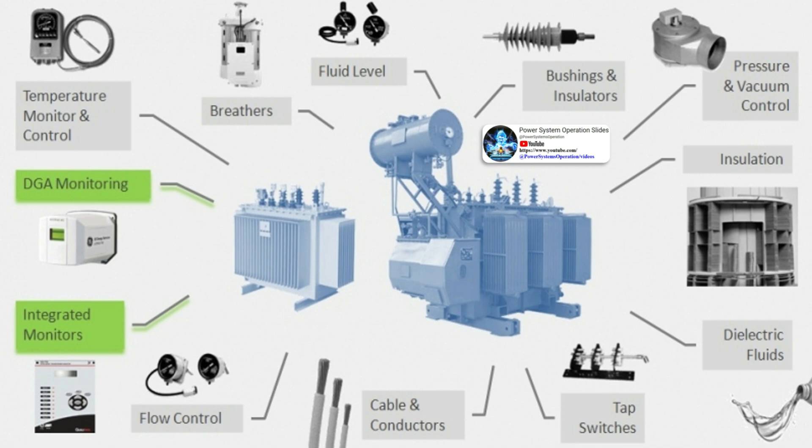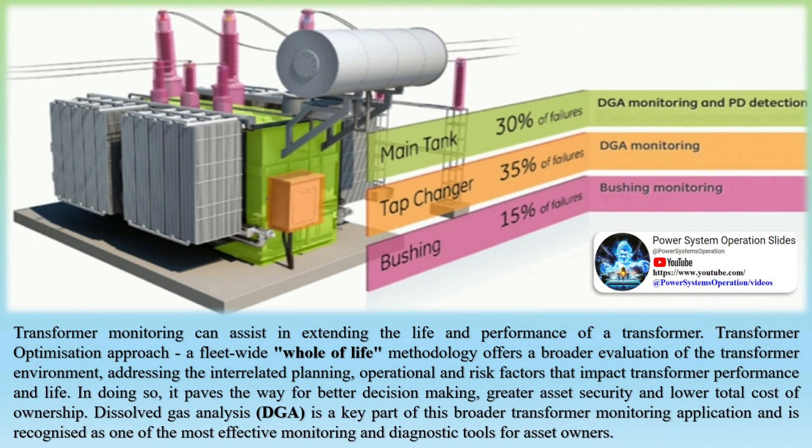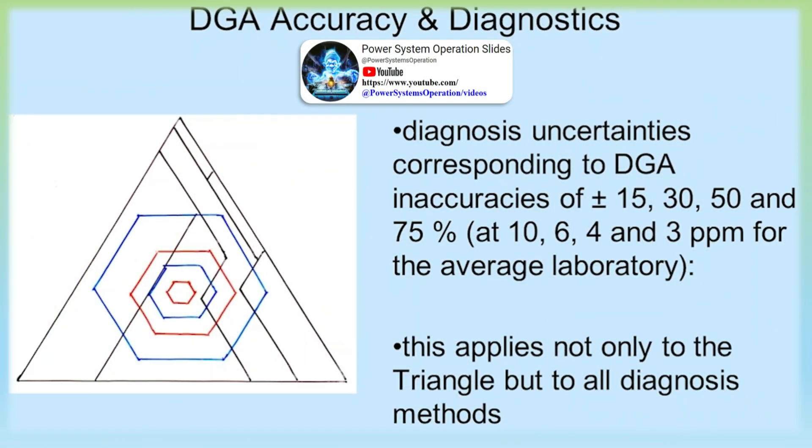Most transformer owners rely on DGA via annual lab sampling, while others utilize online DGA devices on problem assets or larger power transformers. The value of DGA is accepted as a means of periodic checks on transformer condition or post-mortem evaluation. However, the widespread use of online DGA monitoring across an entire fleet is where the true value lies — not in post-mortem, but in prevention and management, helping to maximize asset availability and security while minimizing premature aging and catastrophic failures.